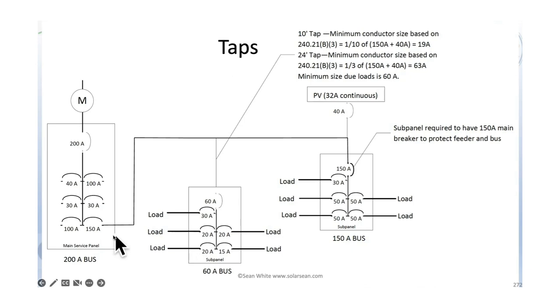And so let's look at this position here. So we've got the 150 plus the inverter current, 125% of 32 is 40. So 150 plus 40 is 190. And 1/3 of 190 is 63 amps.